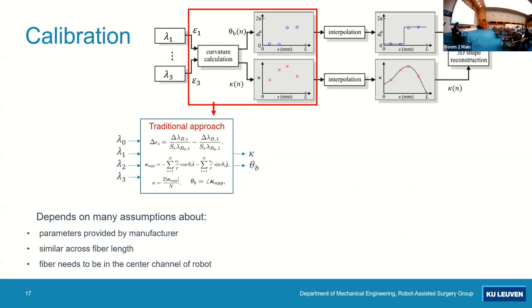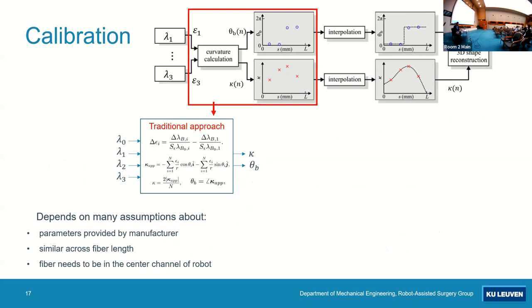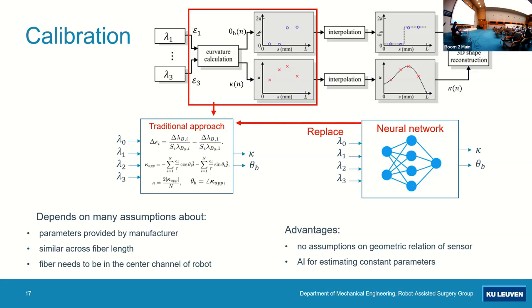We initially tried a traditional approach, trying to identify all these parameters one by one. That's time consuming, so our PhDs were more interested to just throw it in a network. They train with many examples, and the network does the calibration of these parameters. We don't have to make assumptions on the geometry, and we're estimating more or less constant parameters over time. We got excellent results. Here you see these fibers, and we're measuring tip position error, bending these systems and having errors below one millimeter.